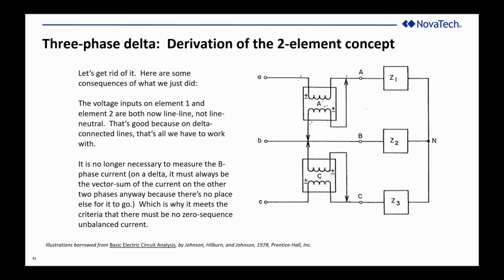My B-phase wattmeter fell out, and the B-phase current, as you can see from this diagram, doesn't enter into the calculation of 3-phase watts at all. Now that is not, I think, counterintuitive. That, I think, is intuitive when you look at it this way. If I've made the premise that I have no neutral current, or in a delta-connected system, I have no neutral conductor, so there's no place else for the current to flow.